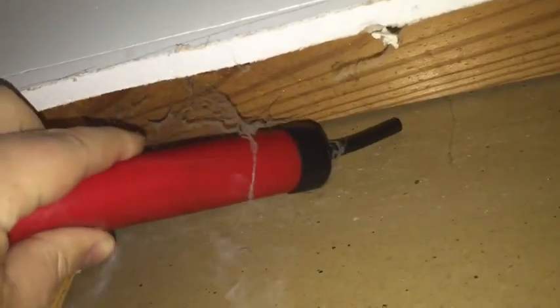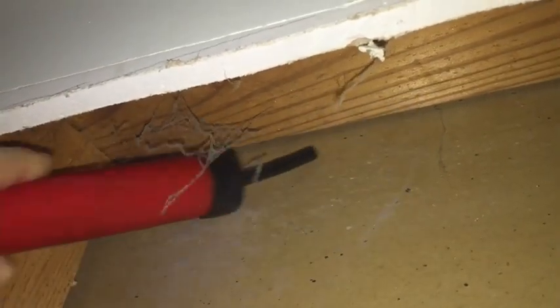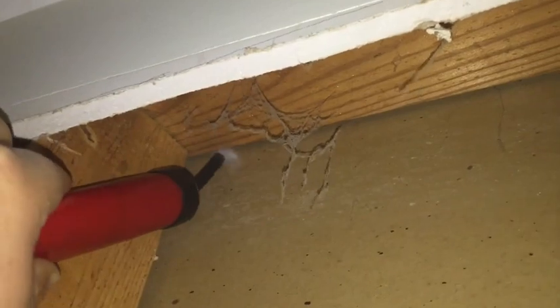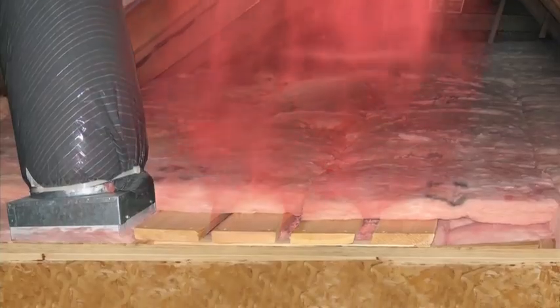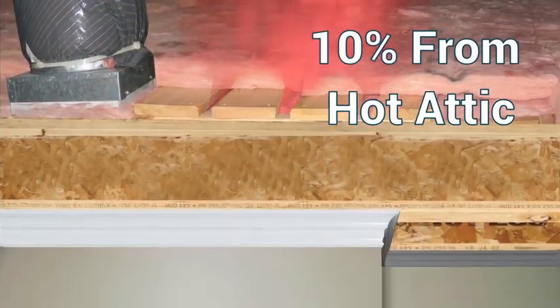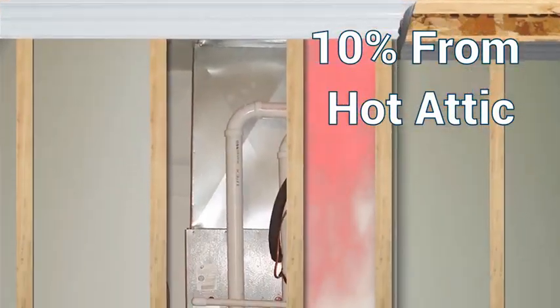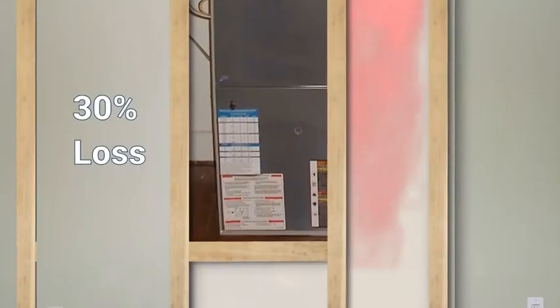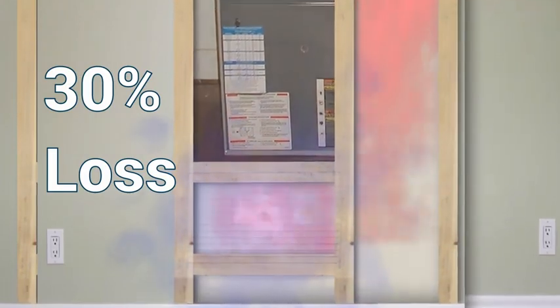Now, some have the misconception that return side leaks inside the house don't matter. True for some, but not for many. Many of these return leaks, both small and large, inadvertently draw dirty, hot or cold, humid or dry air from the attic, crawl spaces, or in the outside walls. This causes higher utility bills, poor humidity control, poor air circulation, dust, and unhealthy indoor air. Remember that if just 10% of the return air is sucked down from a hot, humid attic, it will drop the efficiency and output of an air conditioner by an astounding 30%.